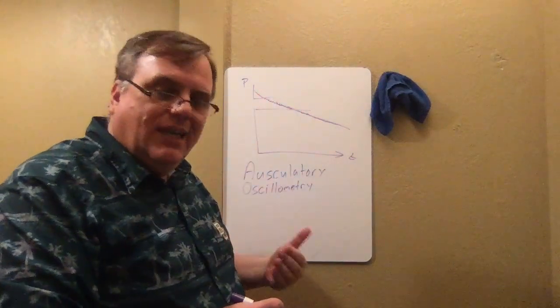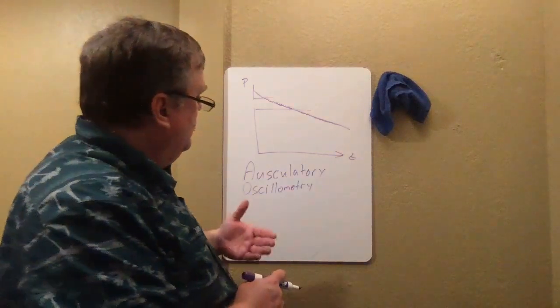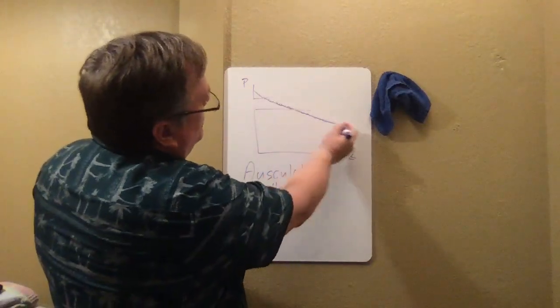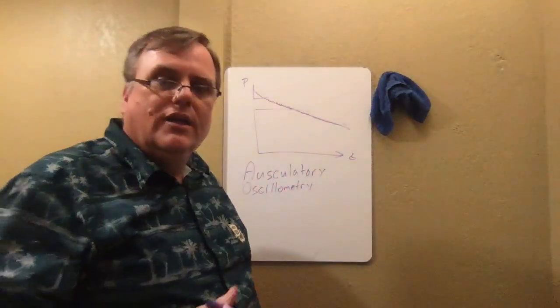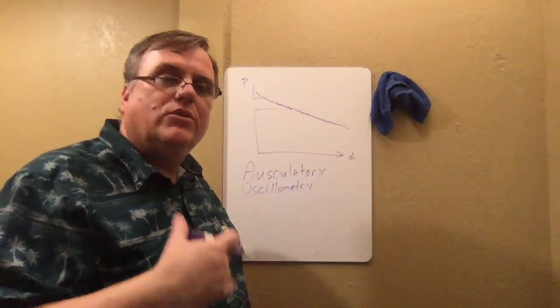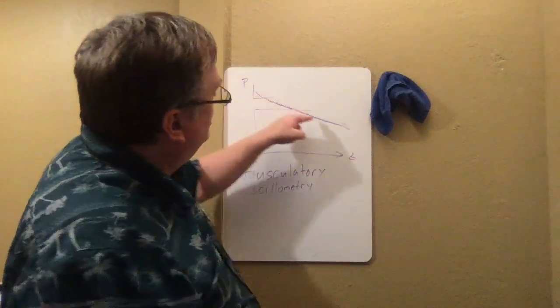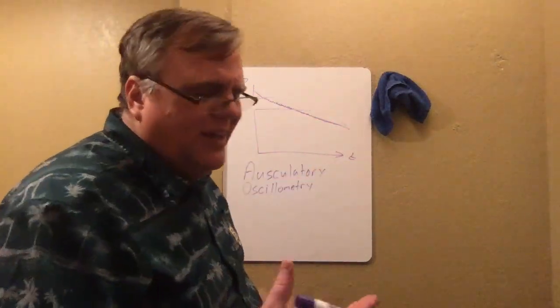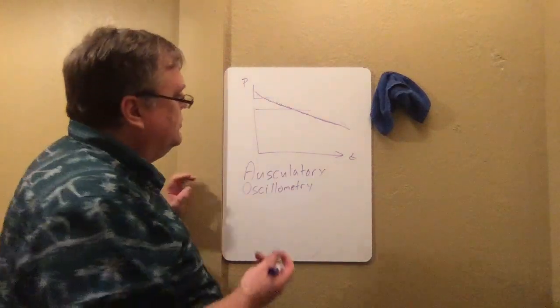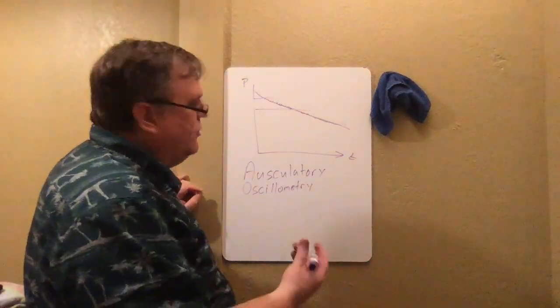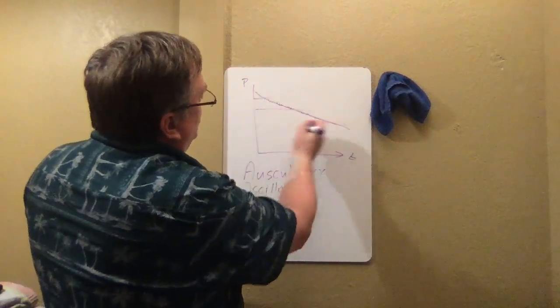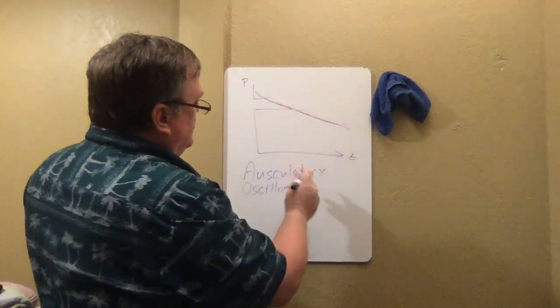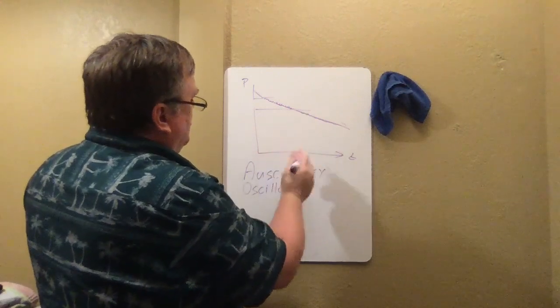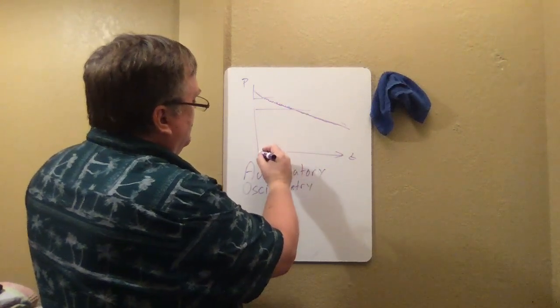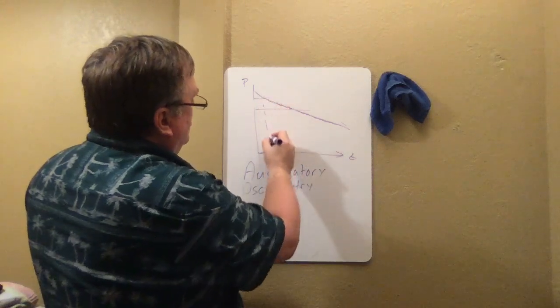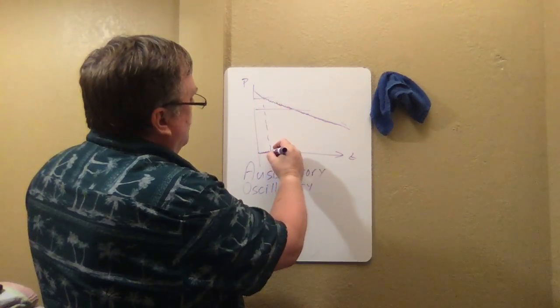And then to get the actual waveform, what you do for oscillometry is you take this, the main wave that it's imposed on is a pretty slow moving one. So if I hit it with a high pass filter, it'll basically knock this baseline out. Typically somewhere around half a hertz is good for this. So a high pass filter with a cutoff around half a hertz, and this whole baseline will go away, and then you just amplify these waves up. And what you'll see in its place is now it can go above and below. You'll see little tiny waves coming in, and it'll start growing.